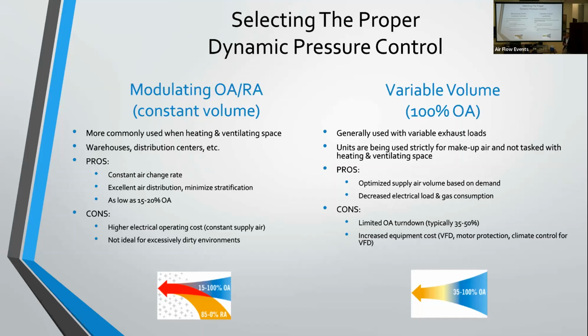It used to be outside air return air units. We still see a lot of outside air return air units, and I'm not sure if that's specifically just because of the applications that we see more of. It'd be like you said, because of the equipment costs, the cost of VFDs dropping. That's one of the disadvantages of those system types: you've got VFD costs, you've got motor protection, you've got VFD climate control, sometimes line reactors. So there is a higher initial cost with those setups.